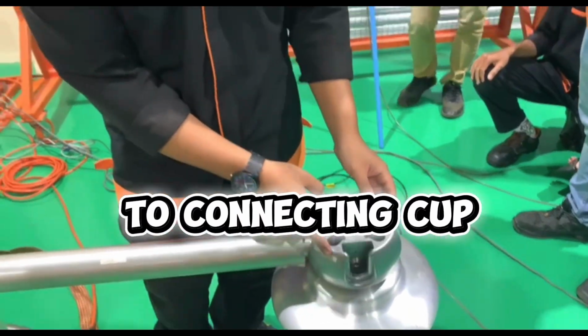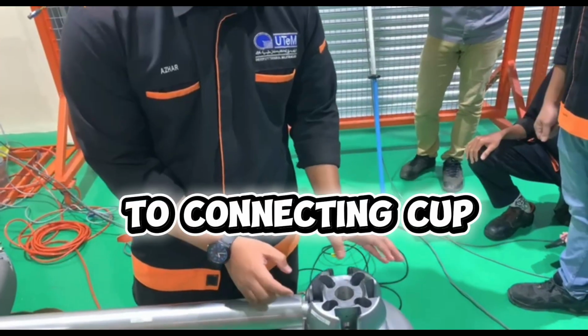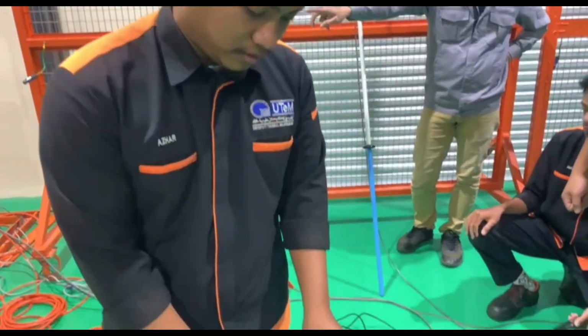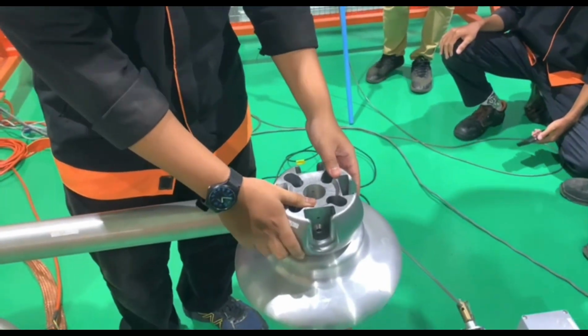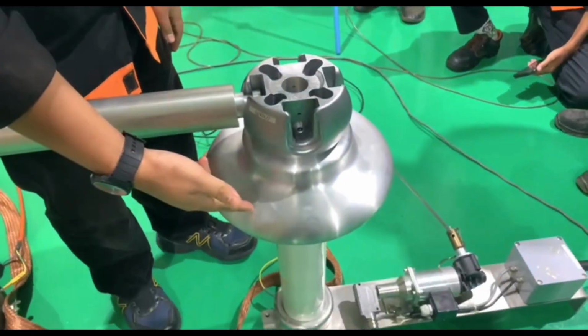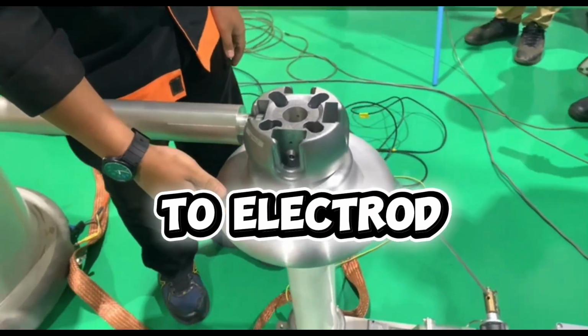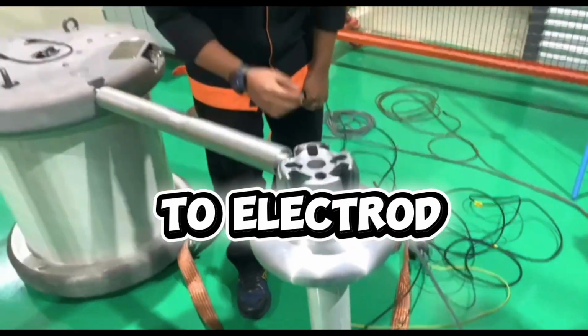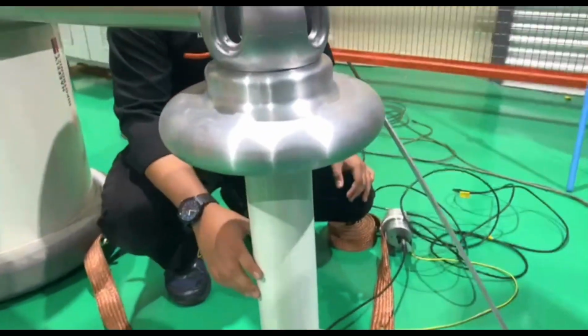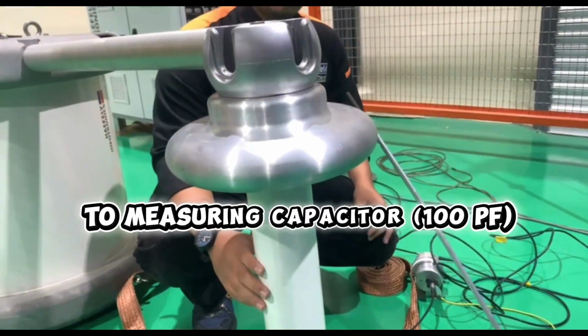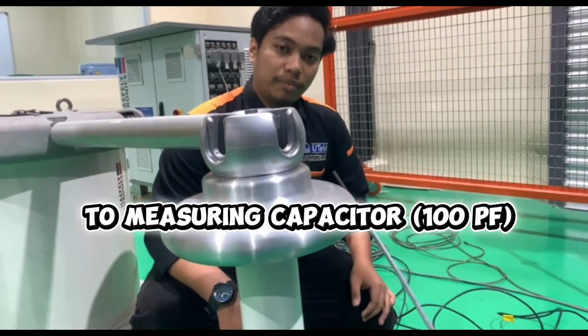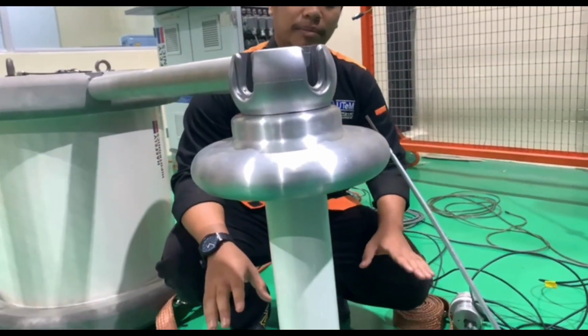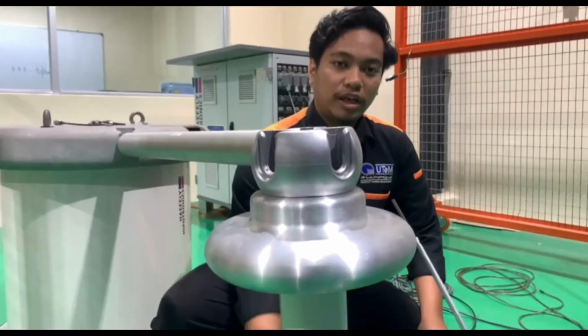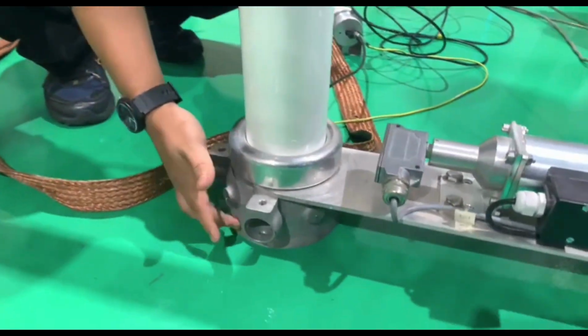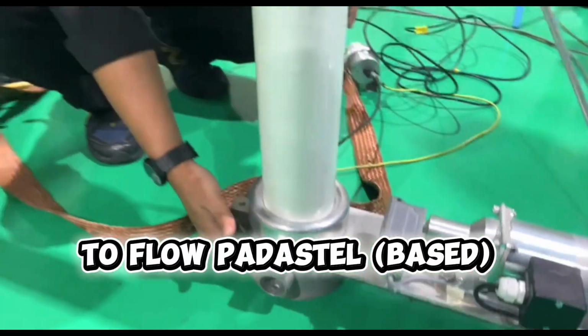This is a connecting cup. To install this, we just slot in all the equipment. Then we have the electrode, and below the electrode is the measuring capacitor, which we use at 100 picofarad. The base of this whole equipment is the floor pedestal.